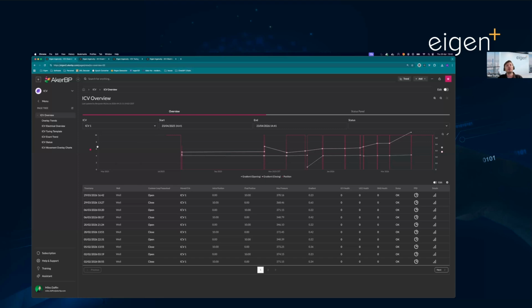Behind the scenes, we are running a simple Python script that is monitoring these .event tags in the system. These event tags record raw hydraulic valve movement, meaning that you don't have to process large volumes of data. If you need to do a backfill, you can just say, well, I want to query 3 years' worth of data, and the only raw points you'll get are valve openings or closings. That script runs in our infrastructure. We've used it many times for very similar use cases to track blowdown valves, heat trace, gas detection.